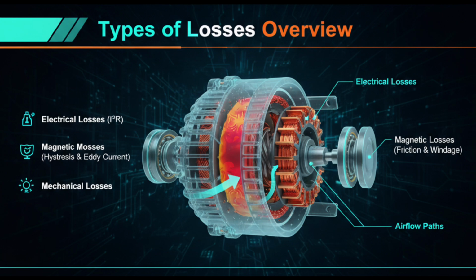All of these losses add together to form the total losses of the alternator, which reduce the useful electrical output and lower efficiency. For marine engineers, understanding losses is essential because excessive heating can lead to insulation breakdown, bearing damage, and unplanned generator shutdowns, situations that are extremely critical when the ship is at sea.